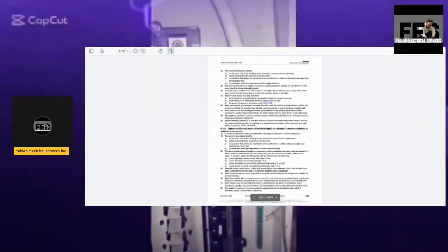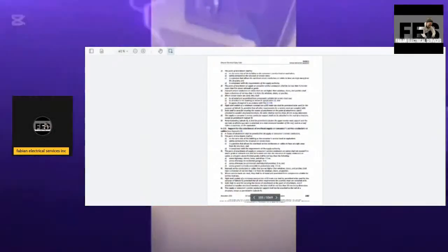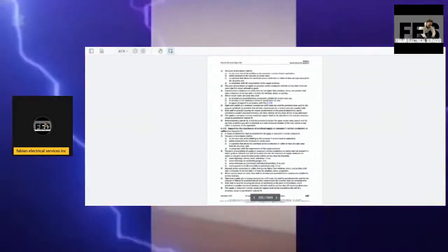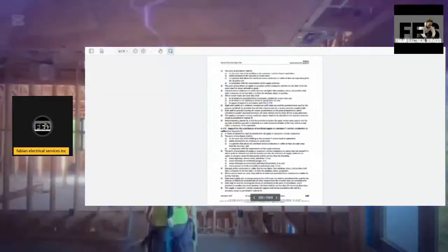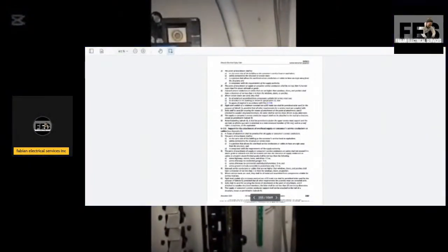Consumer service conductors or cable shall not exceed 9 meters above grade or sidewalk and shall be located such that the clearance of supply conductors or cables at any point above finished grade shall be not less than the following: across highways, streets, lanes, and alleys, 5.5 meters; across driveways to residential garage, 4 meters; across driveways to commercial and industrial premises, 5 meters; and across ground normally accessible to pedestrians only, 3.5 meters.